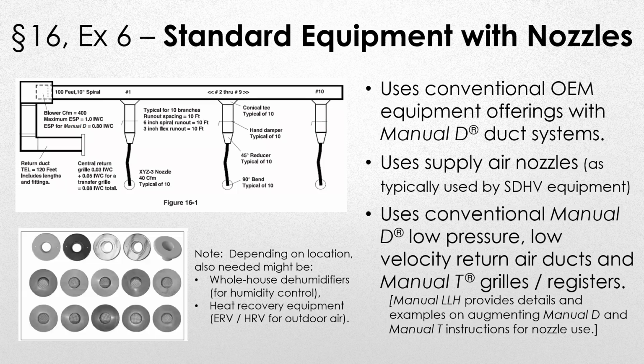We also met with AHRI a month or so ago with a number of the major manufacturers, and they recognize that this is an issue with their equipment, regardless of who the manufacturer is, Carrier, Goodman, Amana, Rheem. They were all there. They understand this is an issue, and they're all working on smaller size equipment options with stronger blowers. So in the next couple of years, we're pretty confident that we're going to see more equipment offerings come out of the major manufacturers that we typically use to deal with the airflow issues, the difference between the latent and the sensible. They know they're going to have to start making that equipment a little bit differently and have more offerings with stronger blowers. But that's not available today. So this is something that you can buy the manual and you can utilize today if you run into a low load home that has low airflow issue.